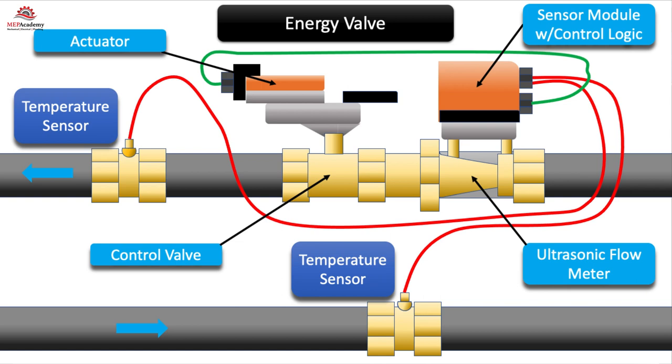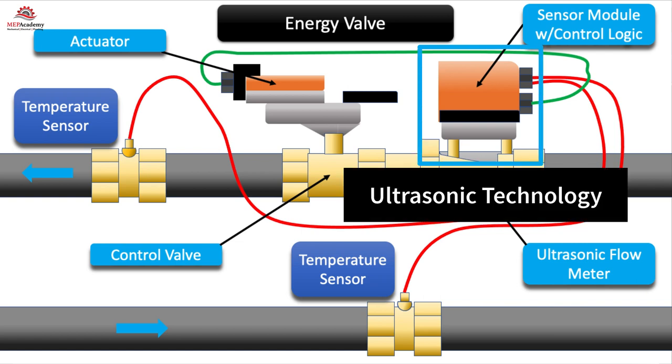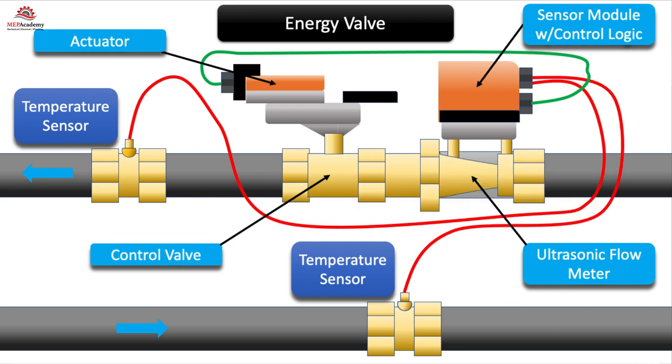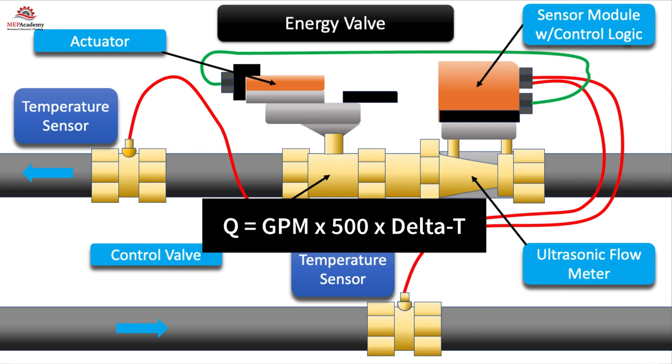By measuring the temperature of the supply and return system water, whether chilled water or heating hot water, the onboard software can optimize flow. Using ultrasonic technology, the energy valve measures the flow through the valve. With the flow and temperature of the supply water circulating through the valve, calculating the total energy is a simple formula. Q equals 500 times GPM times delta T.